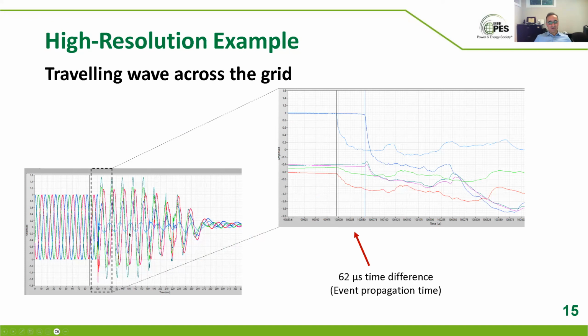Same thing, let's look at it with a fault. Here is a fault. We look at that early part of the fault and zoom in quite a bit right at that transient. And this shows basically there was a fault on B phase. The time difference between the traveling wave arrival at the two terminals, the two ends of the line, is 62 microseconds. For this particular line, we knew the line was about 80 microseconds long, meaning a traveling wave takes 80 microseconds going. For those of you who are not as familiar with traveling waves, in a simplified way, not getting into modes and details, when a change happens on the line, that travels to the two ends. That's like a step function.